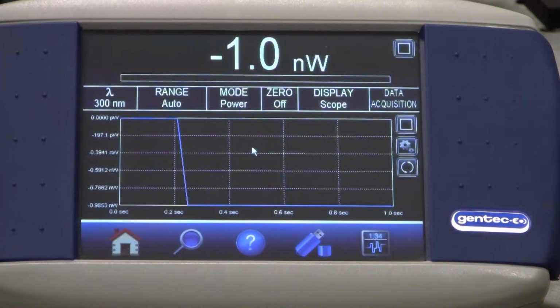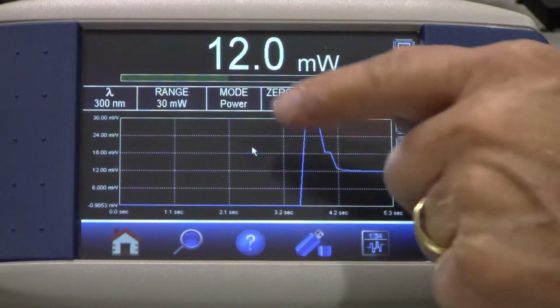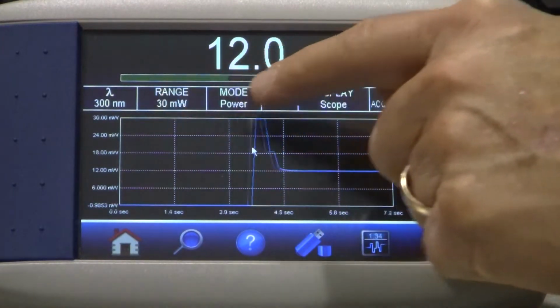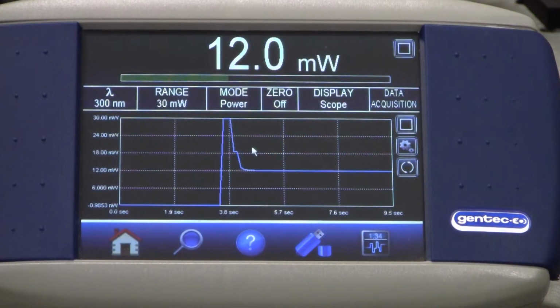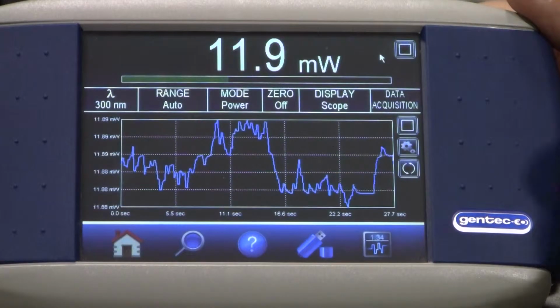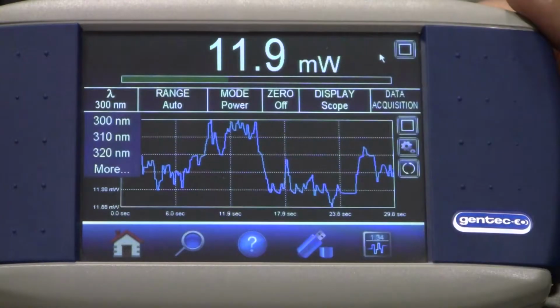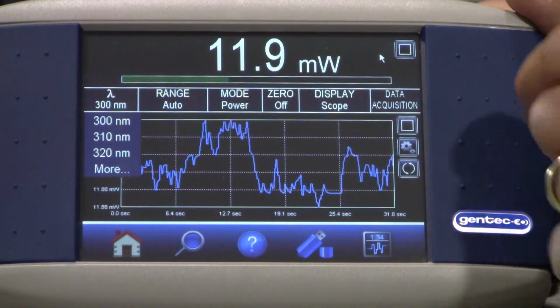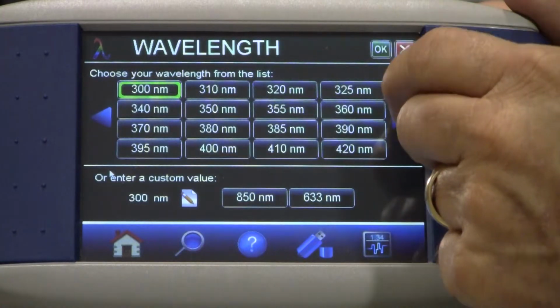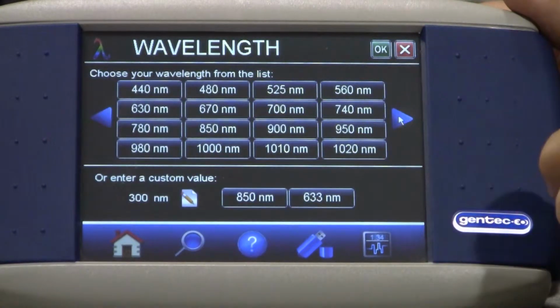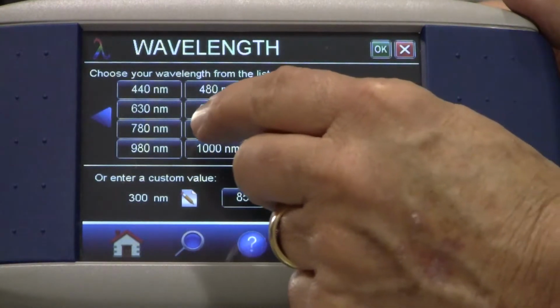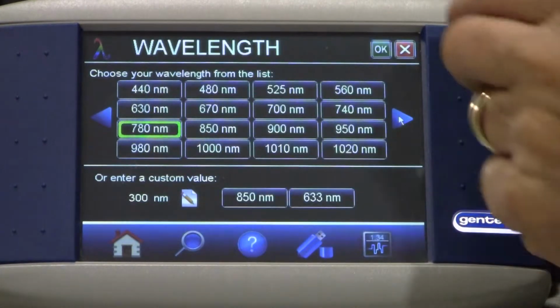Okay, we're now measuring power, but not correctly because the default wavelength for the PH100 probe is 300 nanometers. We need to set the wavelength to 780 nanometers. Here's how it's done. Touch the wavelength button. You'll see a drop-down menu with a small selection of values, but not 780. So select More. You'll see a matrix of wavelengths. Use the right or left arrow to see more options. We'll select 780 nanometers and push the OK button.